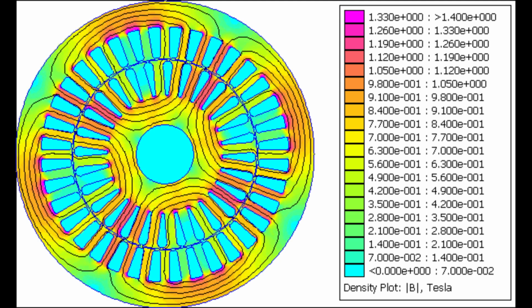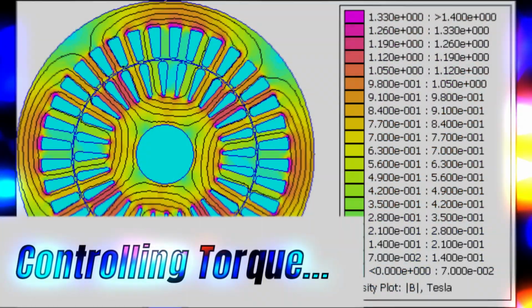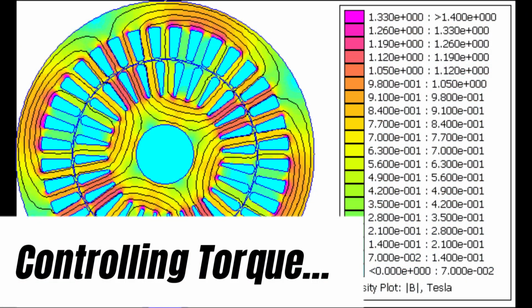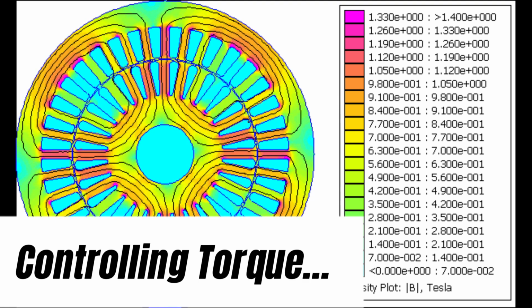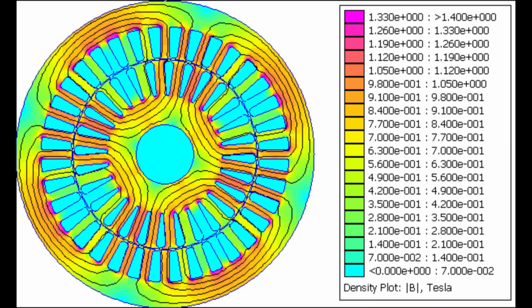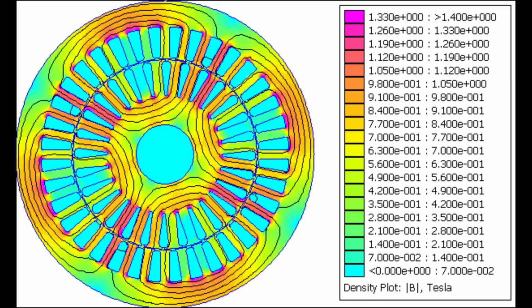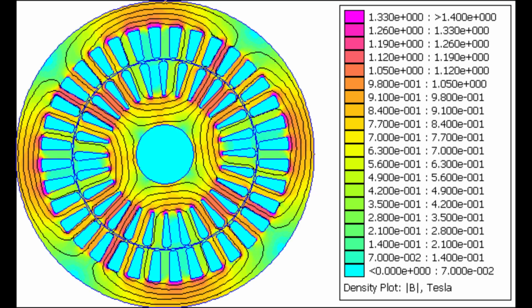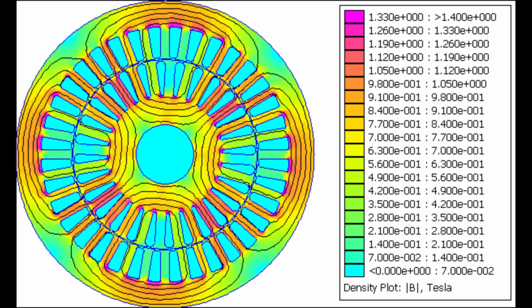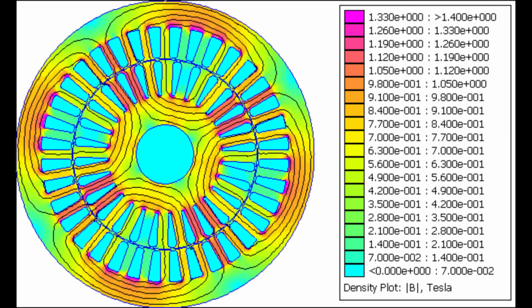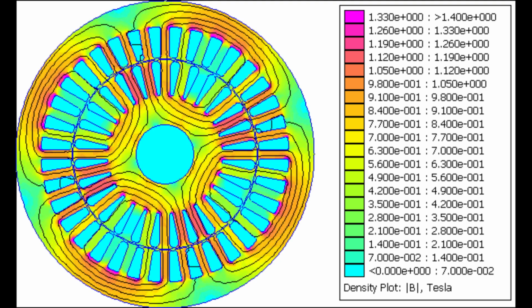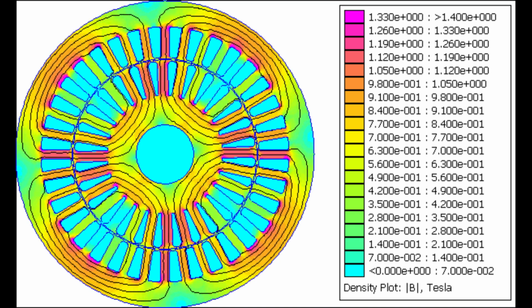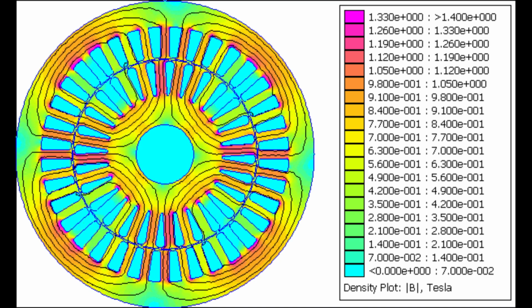Controlling torque. The most common method of starting a polyphase squirrel cage induction motor is to connect the motor directly to the plant distribution system at full line voltage. In this case, a manual or magnetic starter is used. From the standpoint of the motor itself, it is perfectly acceptable practice. As a matter of fact, it is probably the most desirable method of starting this type of motor.